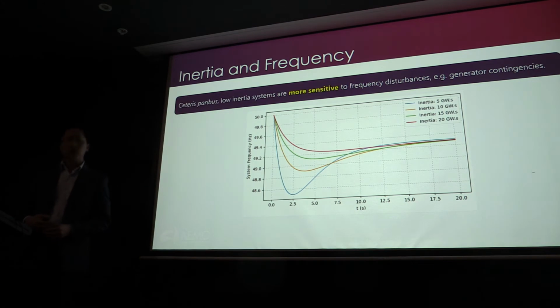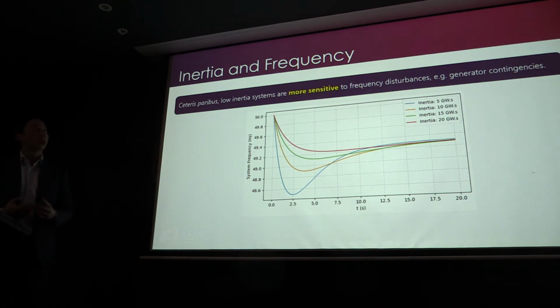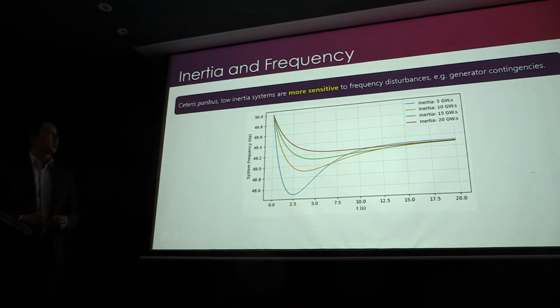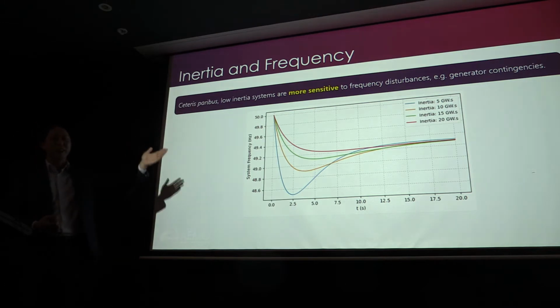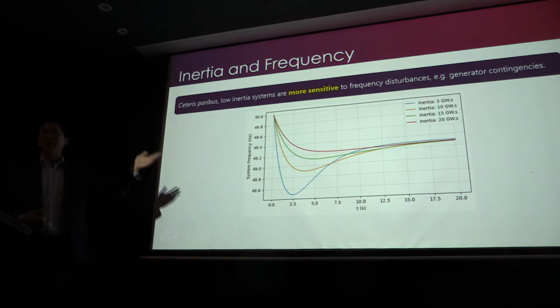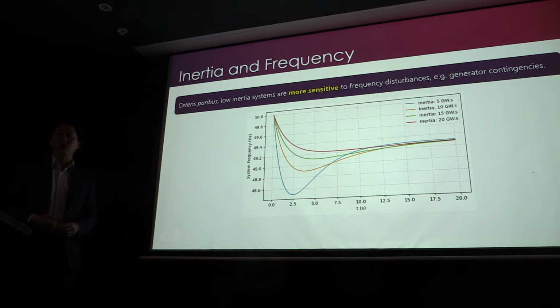And inertia is related to frequency, as we talked about. So ceteris paribus, all things being equal, low inertia systems are more sensitive to frequency disturbances. So here, this graph just tells the picture. With high inertia, 20 gigawatt seconds, let's say, not super high, but higher inertia, you have a better frequency response. As you get lower and lower, you get much lower frequency nadirs and a worse sort of frequency performance.